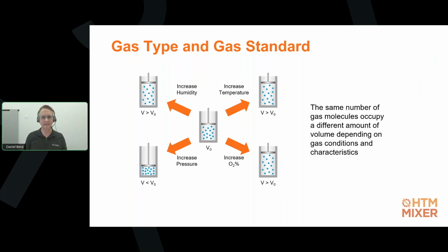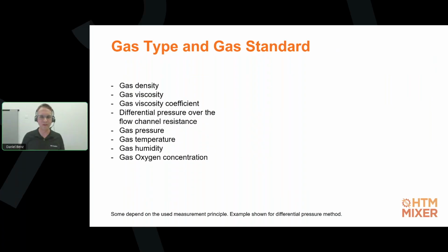So this means that the same number of gas molecules occupy a different amount of volume depending on gas conditions like temperature and humidity, and characteristics, for example, how much oxygen is in the mix. Because of that, gas flow measurement is kind of complex. The gas flow analyzers need to know many different parameters to finally calculate flow and volume. There's a whole list. Don't worry, we'll not go through all of them, but the first three are the gas density, viscosity, and the so-called viscosity coefficient. We are not going to set these individually. They are related to the gas characteristics and are defined with a setting we call gas type.